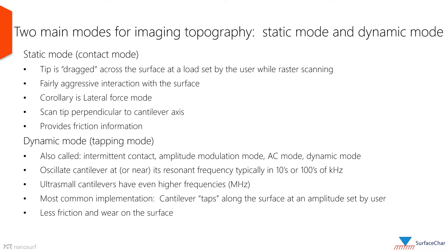Generally speaking, there are two main modes for imaging topography: static mode and dynamic mode. In static mode, the tip is dragged across the surface, applying a certain force set by the user. It is a fairly aggressive interaction with the surface. If the scan is done perpendicular to the cantilever axis, lateral force can be probed, which provides friction information.